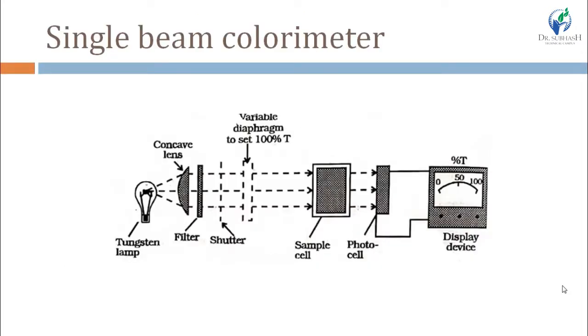This is the single beam colorimeter. It consists of a tungsten lamp as a source of light. The radiation is focused onto a slit by a concave mirror, then passes through a simple absorption filter where only the required wavelength of light passes through and falls onto the sample cell. The sample solution absorbs part of the radiation and the rest is transmitted. The transmitted radiation intensity is determined using a photovoltaic cell and displayed using a digital display or galvanometer. Single beam colorimeters are simple in construction, inexpensive, and easy to operate.